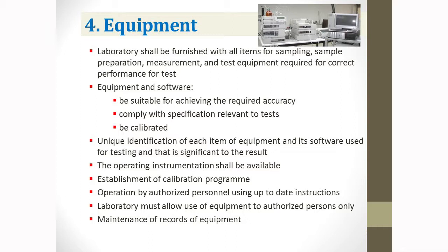For example, for heavy metals testing at low detection limits, you need a certain AAS with the appropriate detection system. You must comply with specifications relevant to the test, and equipment needs to be calibrated. ISO 17025 requires unique identification of each significant item of equipment and software. Operating instructions must be available, and you need to establish a calibration program.